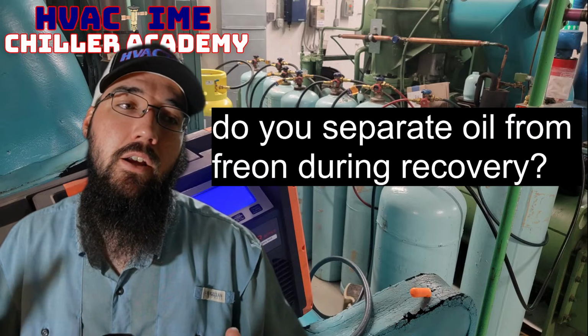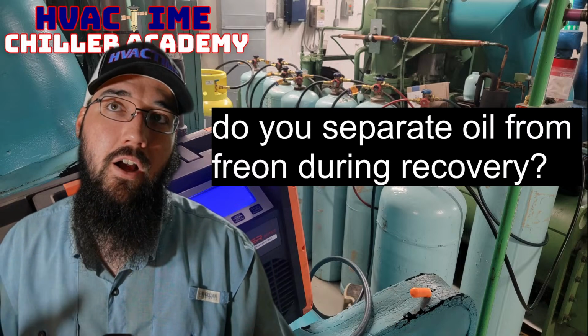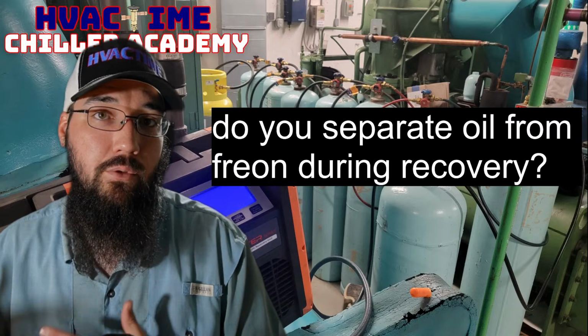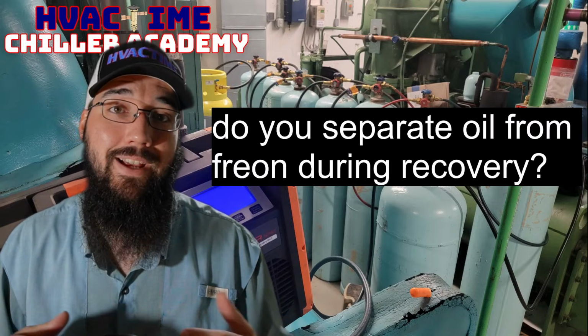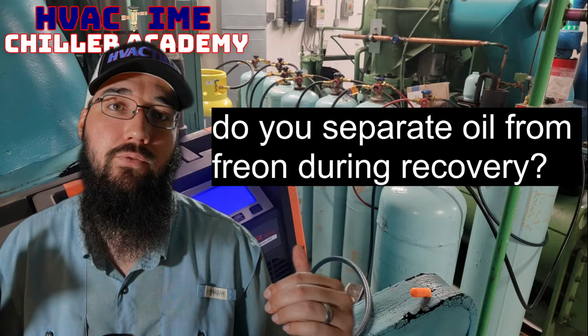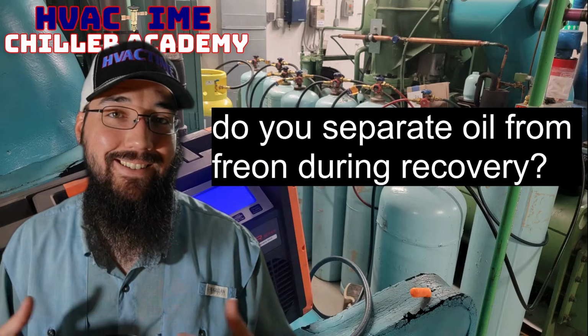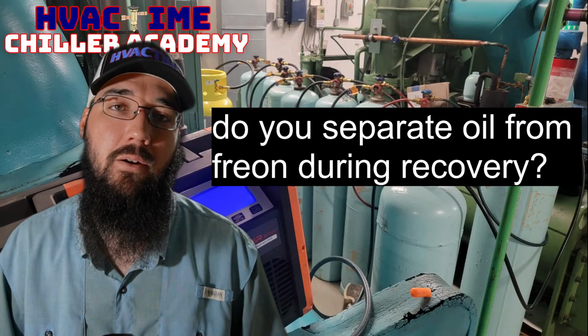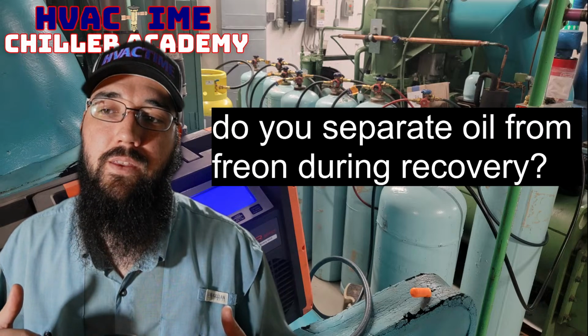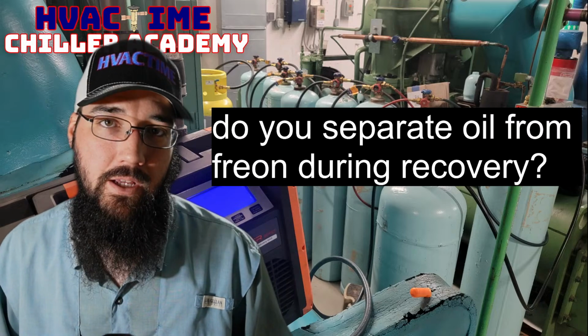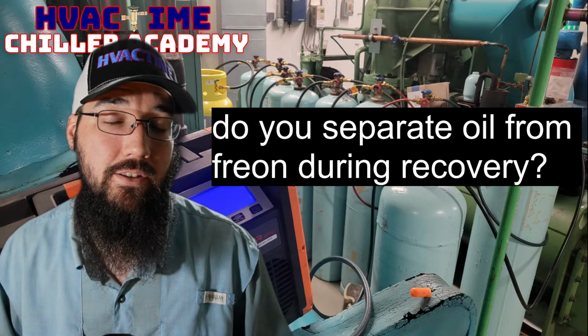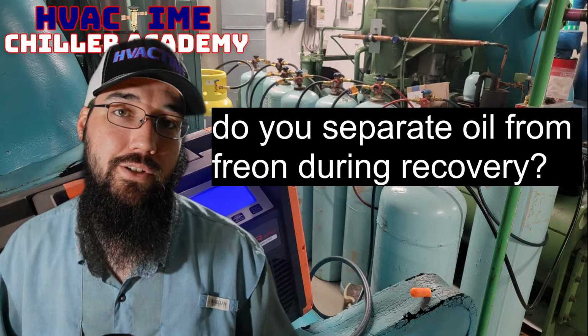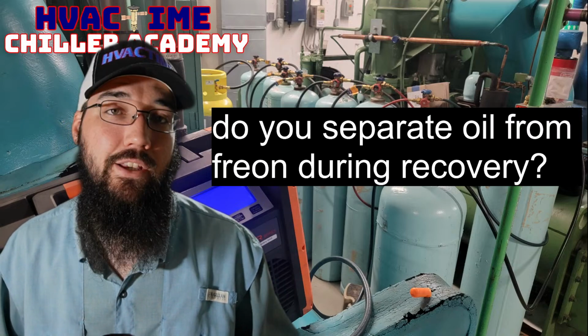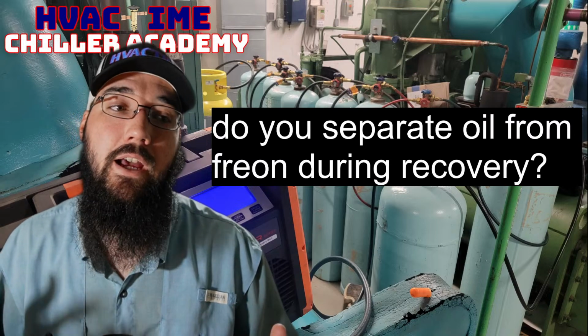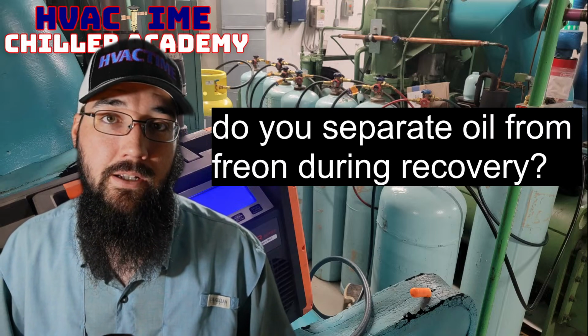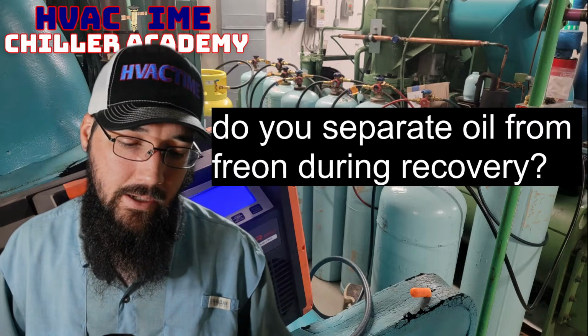If they're going to take that path and not allow me to put clean refrigerant in after a burnout, which has a high risk of future failures and isn't easy to clean those systems up, I'm not going to trust that refrigerant. So if that's their demand and they're not willing to make the budget to pay for new refrigerant, then you get no warranty. If you're not okay with that, I'm sorry, go use a different vendor. I'm not taking that liability on.